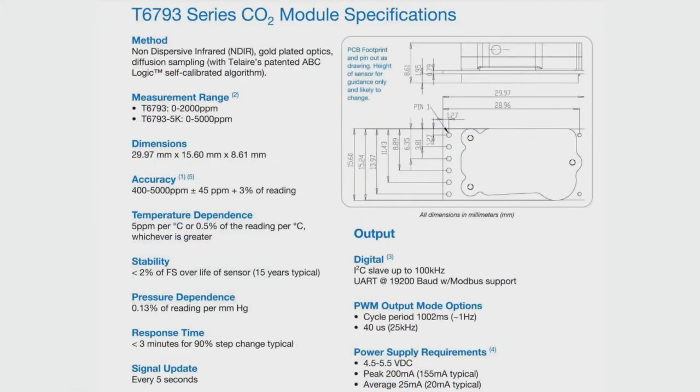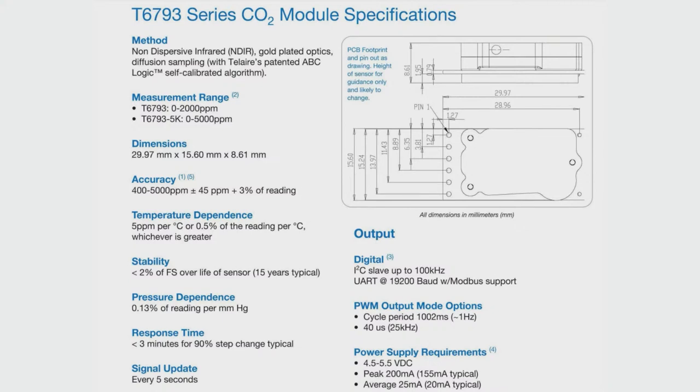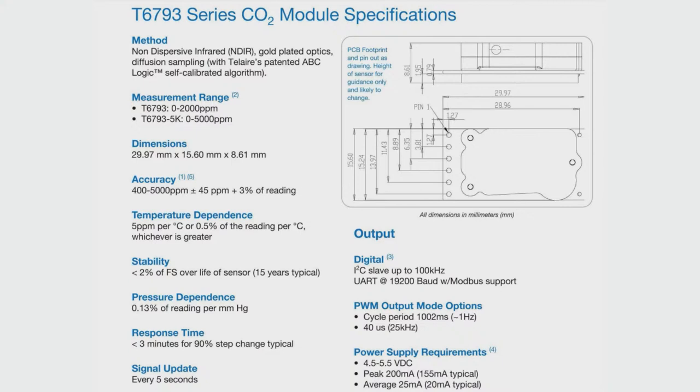So this one, it has really good temperature dependence and accuracy, plus or minus 45 ppm plus 3% of reading, which is really great. You can always calibrate it to be even better. There's a built-in algorithm that if this is being used for outdoor reading or readings indoor where there will eventually have an open window so that the minimal CO2 ppm is 400, it will recalibrate because it does drift a little bit over time.